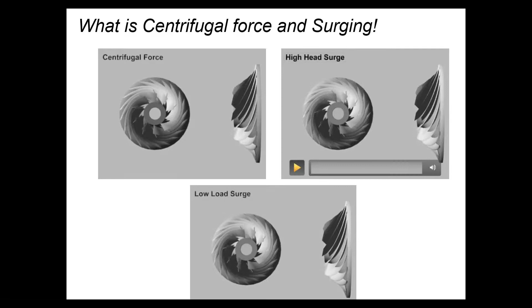So this is the high head surge. Okay, so high head surge is nothing else. Your condenser is sitting at a higher pressure, your compressor is not able to overcome the pressure of that condenser, and there is a flow back of refrigerant happening. So what you're necessarily doing is the impeller is rotating, it is trying to lift the refrigerant, but it is flowing back because the condenser is sitting at a higher pressure. And this is what is being denoted over here.